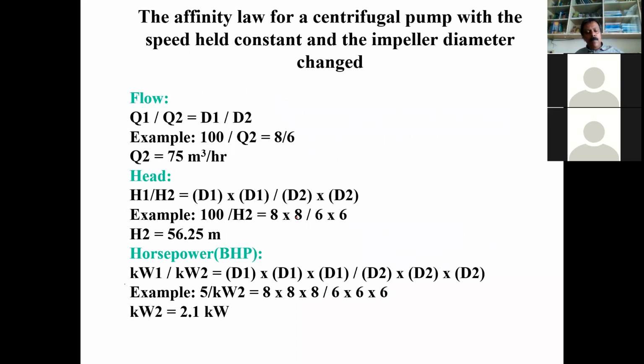So as we have seen, if you have a bigger pump and you want to make it smaller and reduce the power consumption, one option is to trim the impeller. Trimming the impeller means reducing the diameter of the impeller. In a typical pump, the flow is proportional to the diameter, the head is proportional to the square of the diameter, and the power is proportional to the cube of the diameter. So when you reduce the impeller size by 25%, from 8 inches to 6 inches, the power consumption reduces by more than 50%.